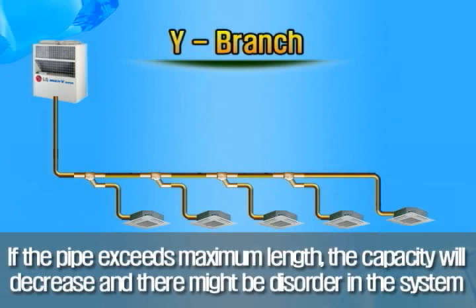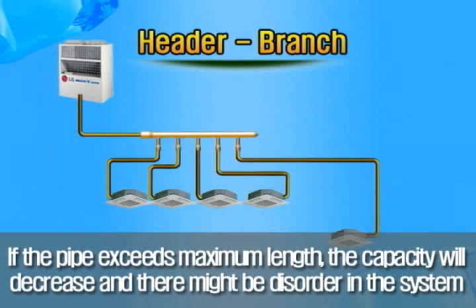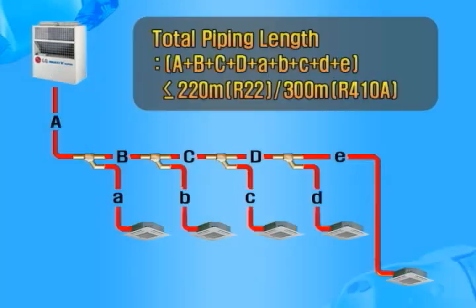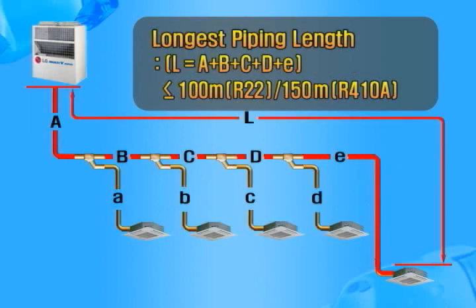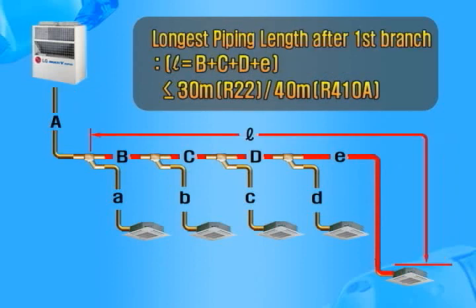Multi-V Plus distributes refrigerant in two ways, Y branch and header branch. The total length of the pipe is under 220 meters for the R22 model and 300 meters for R410A. The longest pipe L is under 100 meters for R22 and 150 meters for R410A. After the first branch, the longest pipe is 30 meters for R22 and 40 meters for R410A.